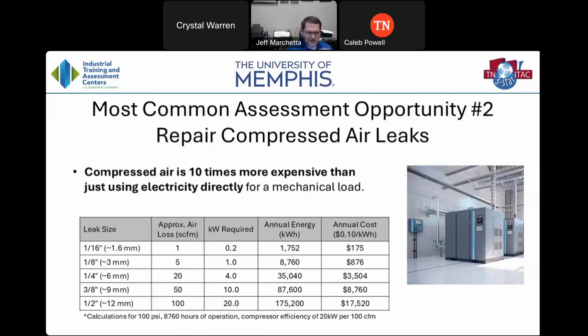The next one we see often is compressed air leaks. If you're in a plant with a compressor, you know the telltale hiss of a compressed air leak, and it may feel futile to continue—if you tried to continuously fix all of these leaks, you'd never do anything else. I understand that feeling of never winning the battle, but the battle isn't to fix 100% of your leaks. It's about finding the ones costing you the most money and getting your leak load down to a reasonable number.